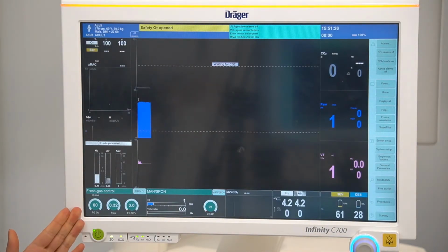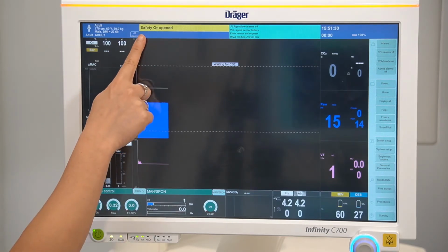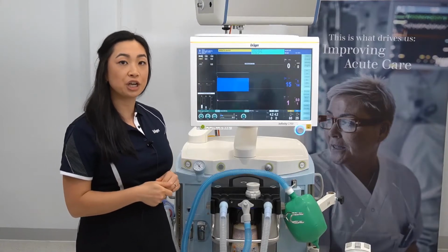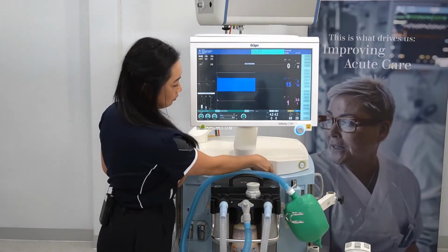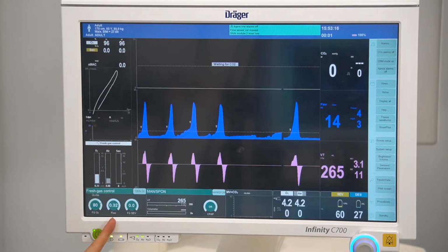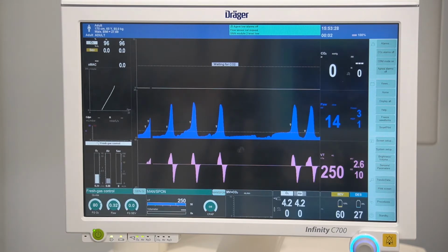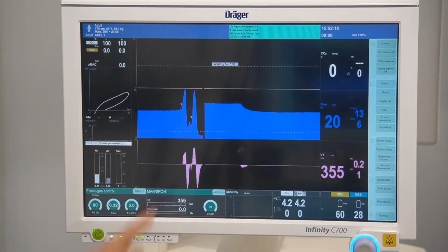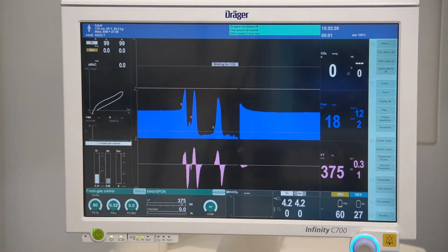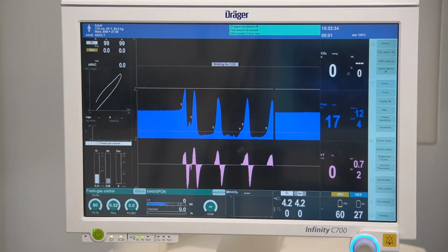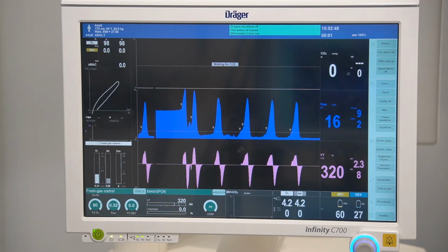Now that you have your electronic fresh gas controls available, you can then deactivate your safety oxygen control. This is done by returning the safety oxygen control knob to the original position. Your DIVA metering modules are also now available, and you can set an anaesthetic agent delivery. As you can see, there are some technical and advisory messages being displayed. The message regarding flow sensor calibration request will be displayed until a system test has been performed. This is when the flow sensors are calibrated. You may also see some technical and advisory messages regarding gas measurement. These will be displayed until the gas bench has warmed and calibrated.